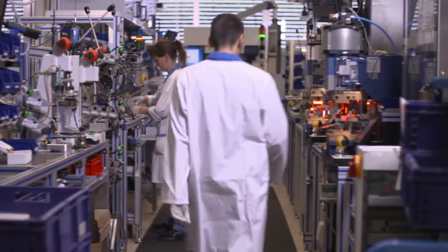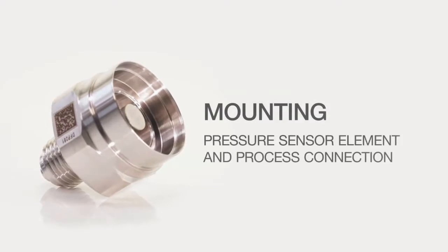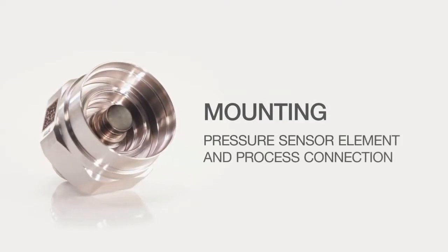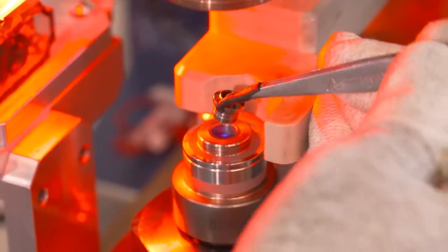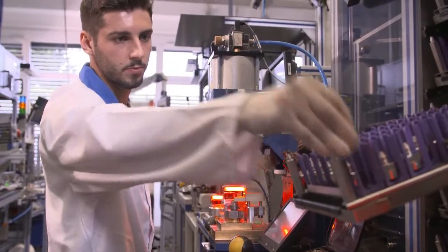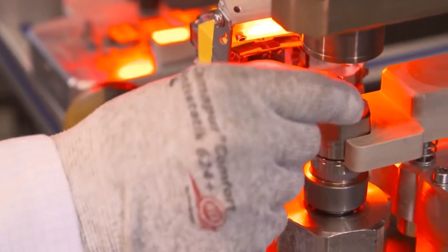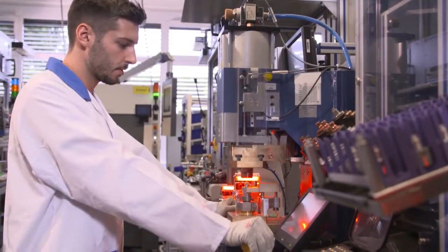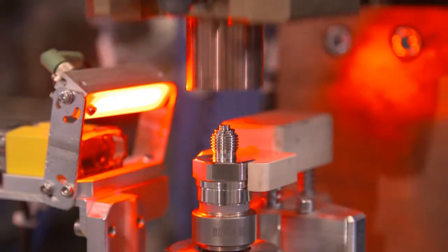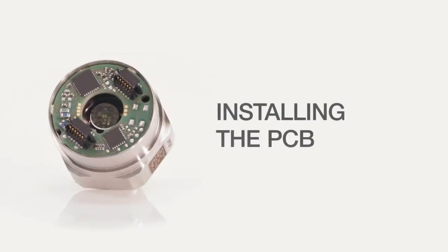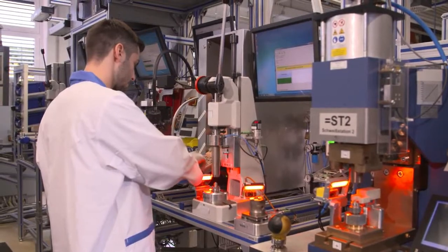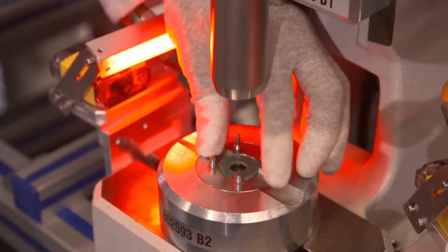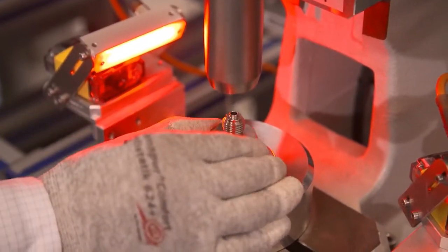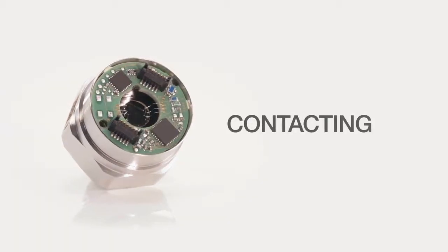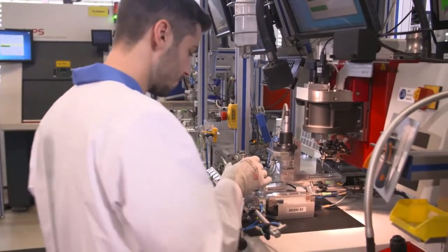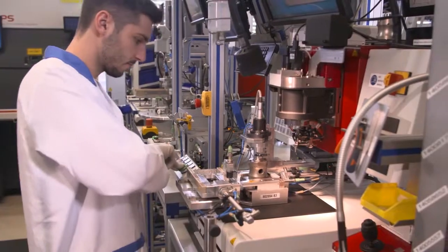Now we see how individual components are assembled in the production. In the first step, the process connection is welded to the pressure sensor element. In the application, the pressure sensor is screwed into the measuring point via the process connection. The pressure sensor element converts the present pressure into an electrical signal. After that, the PCB is mounted. The electronics amplifies and standardizes the sensor signal. Now, only the necessary electrical connection between sensor and PCB is missing.